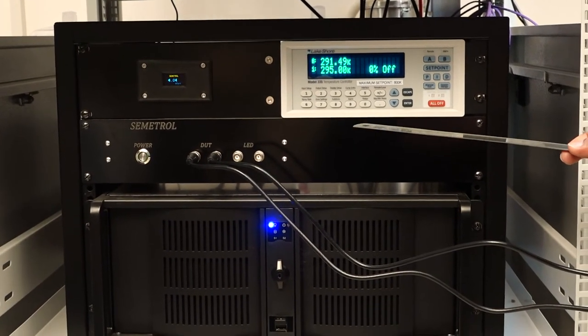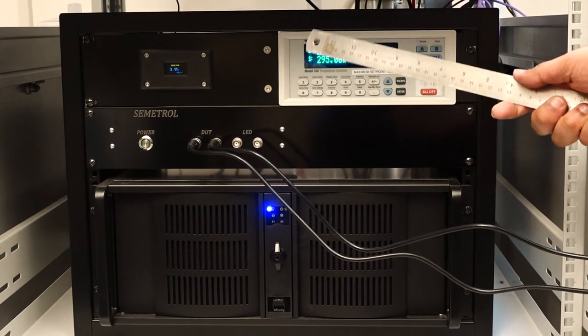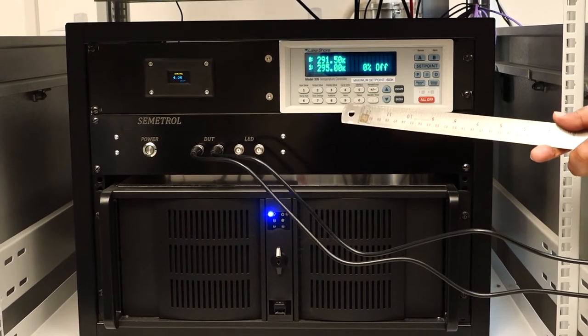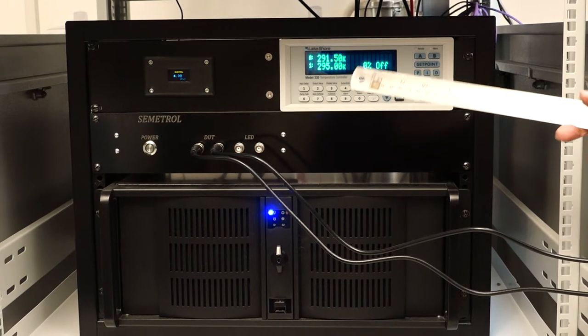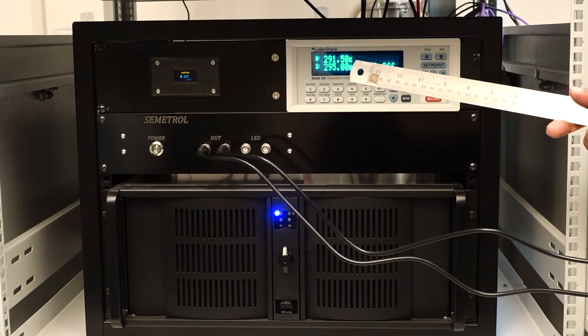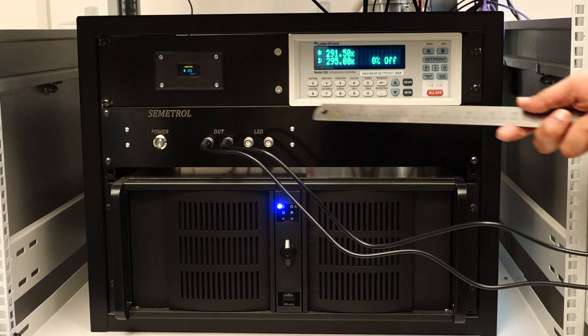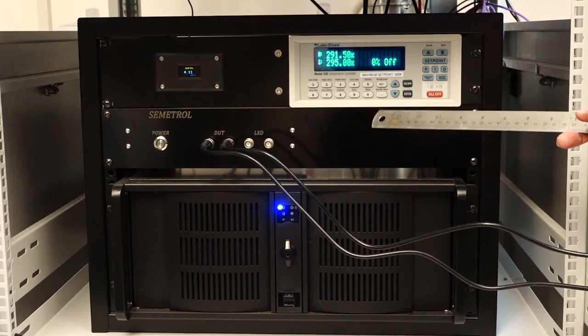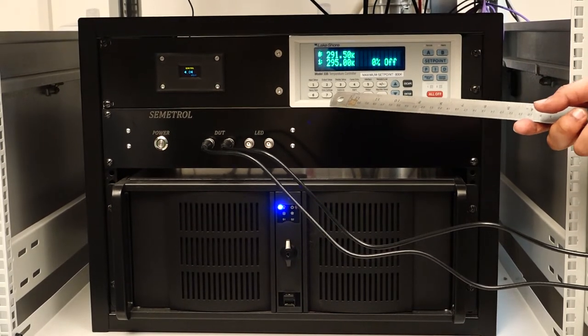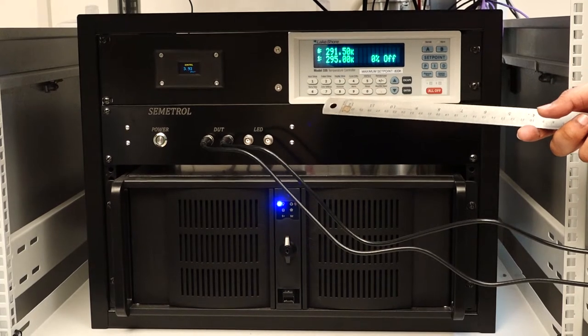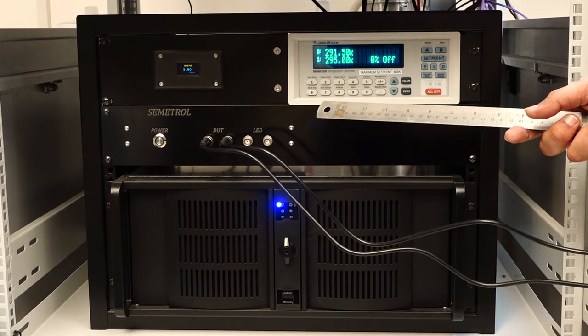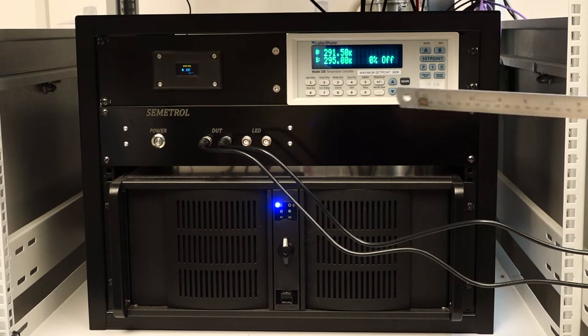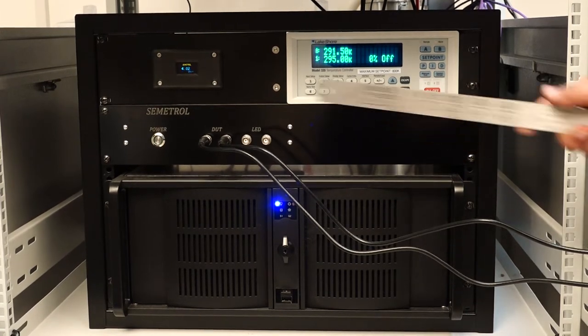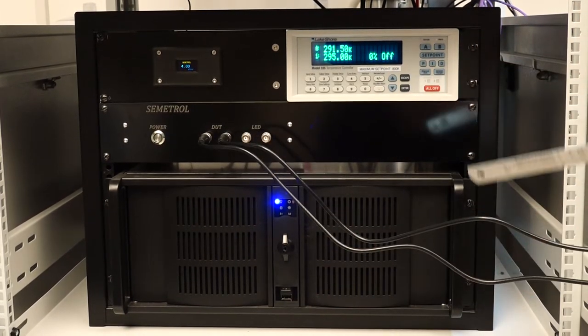Unlike normal CV-IV meters, this source measure unit can measure fast capacitance transient, which is at the heart of DLTS measurements, where we work on the transients that we measure. This fast capacitance meter can measure capacitance in time intervals of less than 0.1 milliseconds. Further, the data analysis is done by the central processing unit housed at the bottom of this control unit.